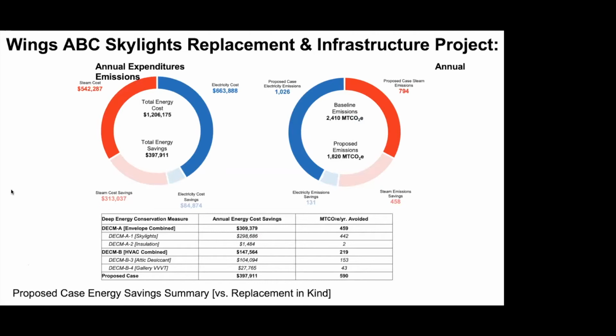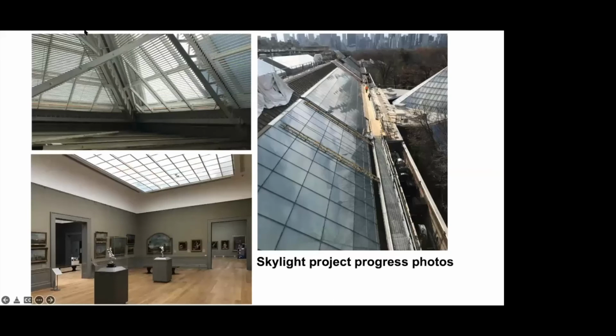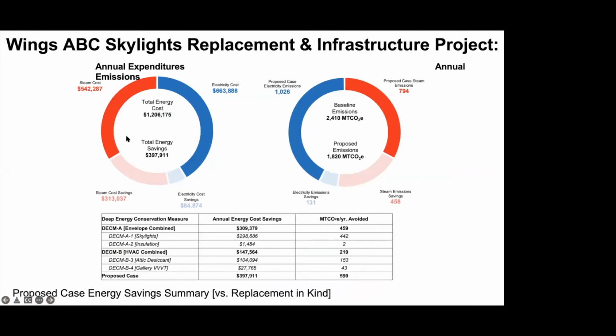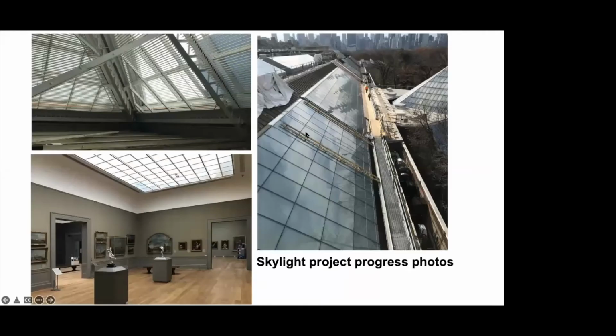As Eric mentioned, there were several different things contributing to this energy reduction, the majority of which had to do with reducing the operative temperature in the attic during winter. What enabled us to do that was to use the desiccant system to dry out the attic such that our dew point was low enough not to have condensation occur. What you could see in those couple charts on the previous slide is, compared to a replacement in kind code compliant baseline that we worked out with DEM and DCAS, it was about a 33% reduction.